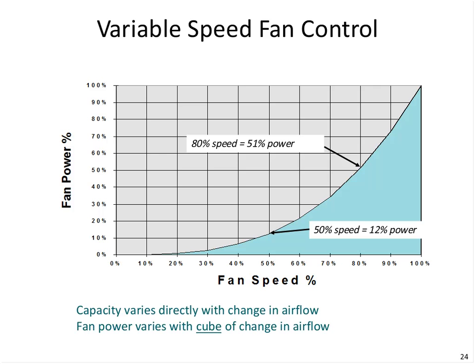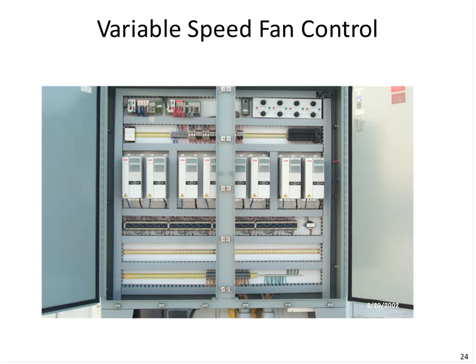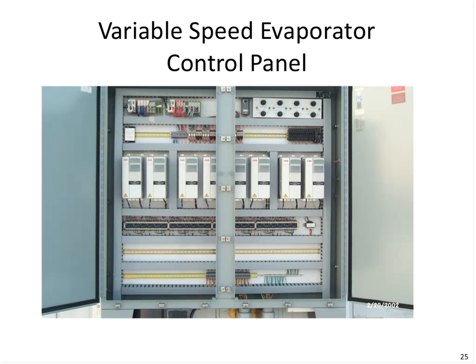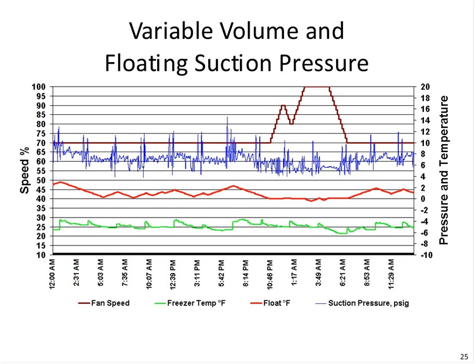The other part is the resetting of the suction temperature. So the variable speed evaporator control panel looks very similar to the condenser because they're basically the same type of control panel. And here's a day in the life of a floating suction pressure. So take a look here at a typical 24-hour period, and let's start from the bottom up. The very bottom line here is the freezer temperature, so notice we're maintaining about -5 degrees. The next line up here is our amount of float that we're achieving, so we'll get back to that in a second.